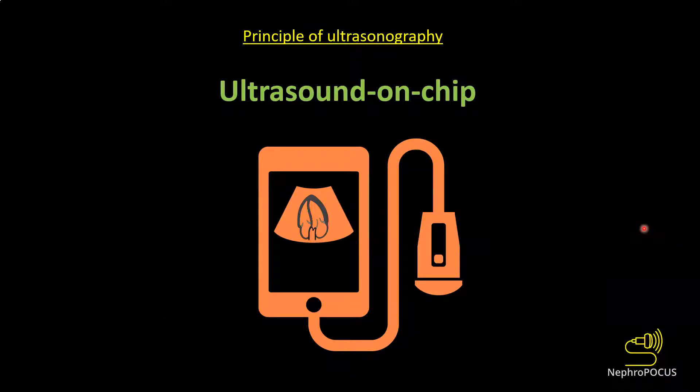Some newer handheld devices use ultrasound-on-chip technology instead of piezoelectric crystals. This technology condenses the properties of different transducers into one device, allowing a single transducer to perform multiple imaging studies. However, the resolution of the images is not as good as piezoelectric probes at this time, though image quality is expected to improve in the future.